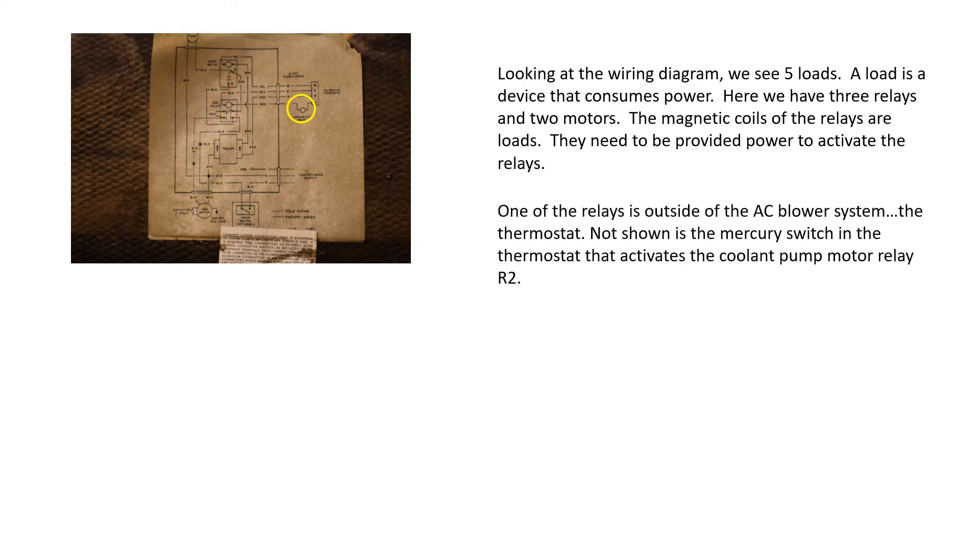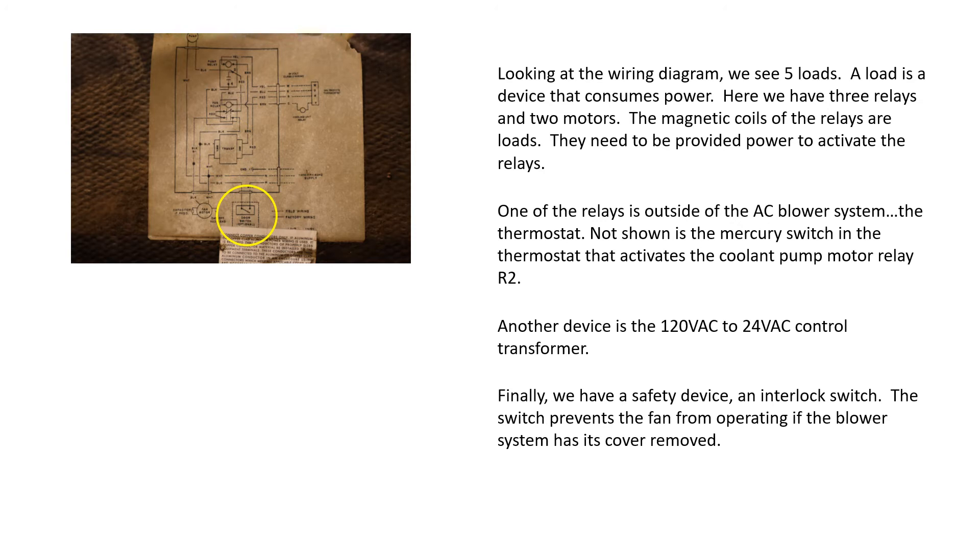One of the relays is outside of the AC blower system, the thermostat. Not shown is the mercury switch in the thermostat that activates the coolant pump motor relay R2. Another device is the 120 volt to 24 volt control transformer. Finally, we have a safety device, an interlock switch. The switch prevents the fan from operating if the blower system has its cover removed.